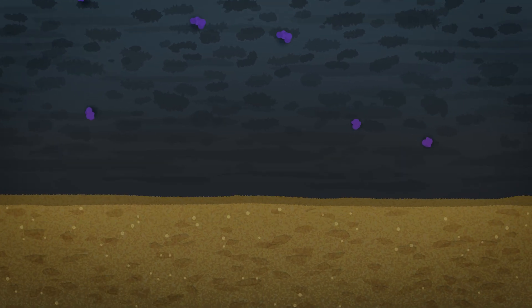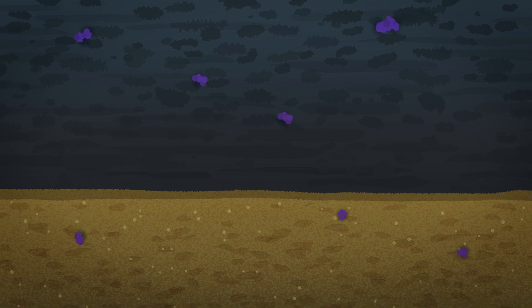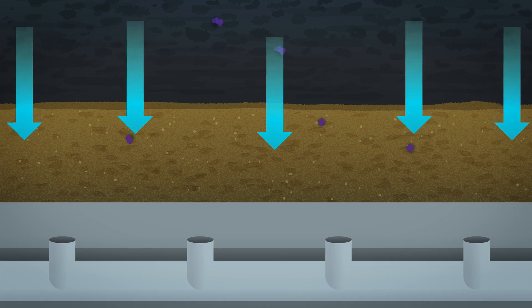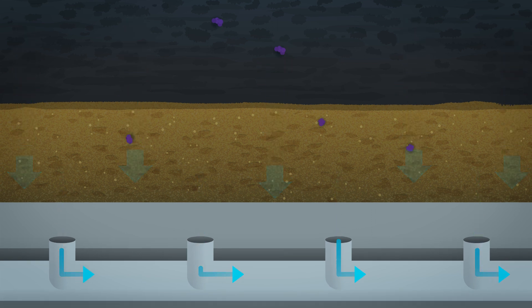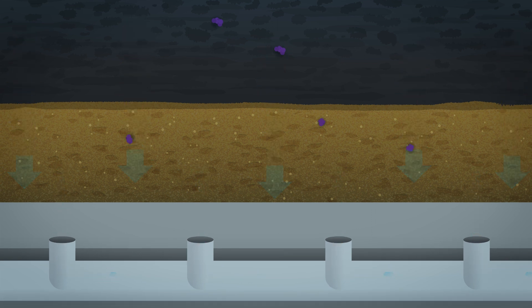The filtration tanks contain a layer of anthracite coal and a layer of sand, known as filter media. As the water works its way down the filter, any remaining particles of sediment get caught in between the cracks of the coal and the sand. The clear water passes through the filter media and exits through pipes at the bottom of the tank.